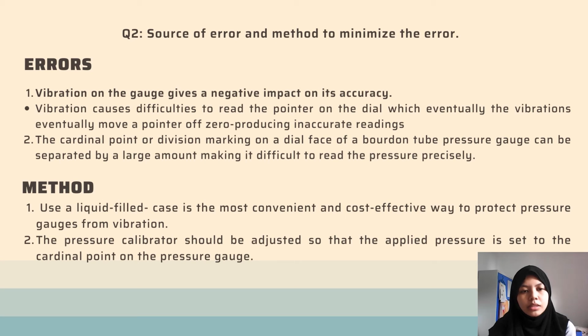Okay, then for question 2, they ask for the sources of error and methods to minimize the error. The first error is that vibration on the gauge has a negative impact on its accuracy. The vibration causes difficulties in reading the pointer on the dial, and eventually moves the pointer off zero, producing inaccurate readings. So the method to minimize that error is to use a liquid-filled case, which is the most convenient and cost-effective way to protect a pressure gauge from vibration.